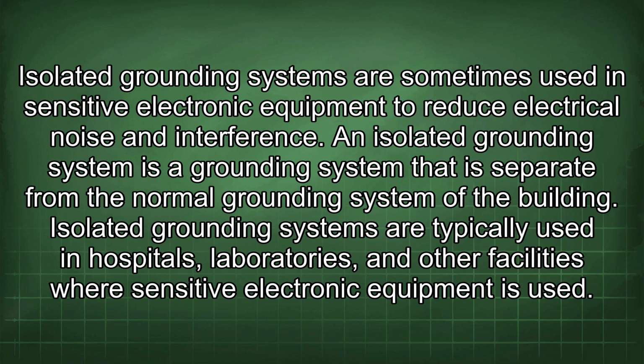Isolated grounding systems are sometimes used in sensitive electronic equipment to reduce electrical noise and interference. An isolated grounding system is a grounding system that is separate from the normal grounding system of the building. Isolated grounding systems are typically used in hospitals, laboratories, and other facilities where sensitive electronic equipment is used.